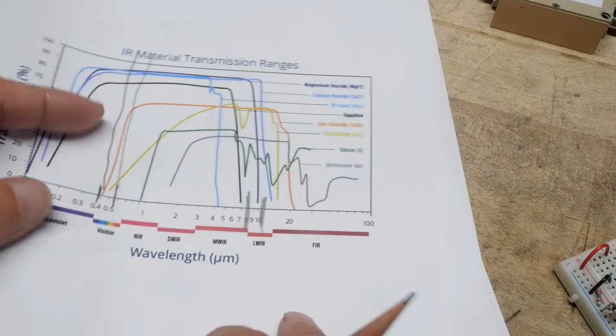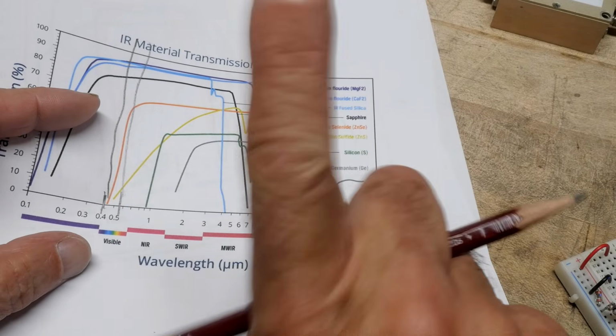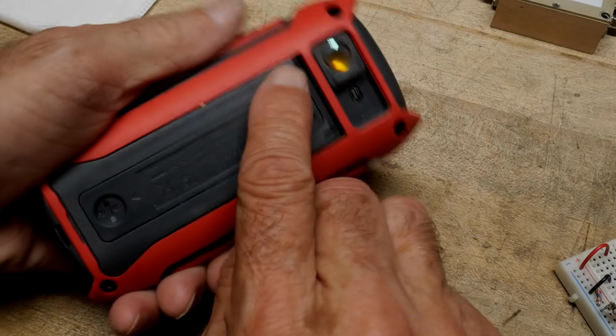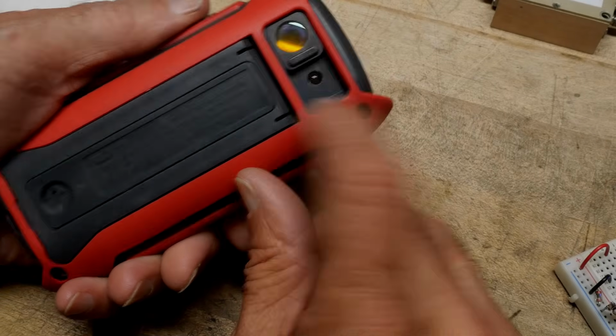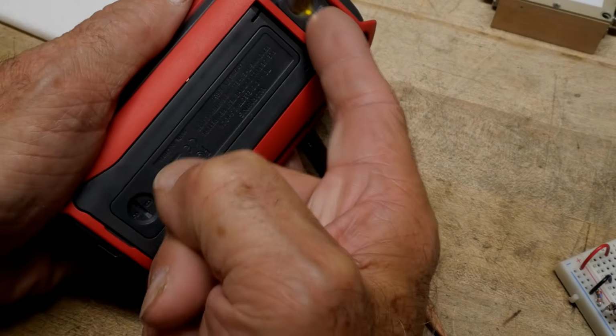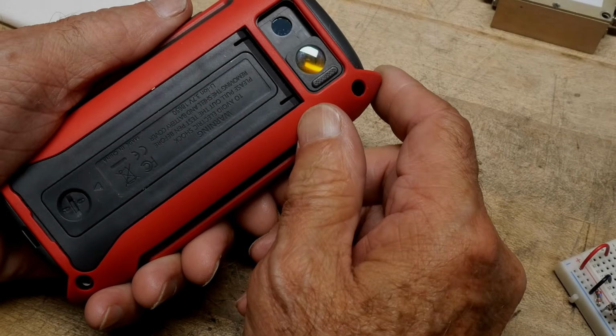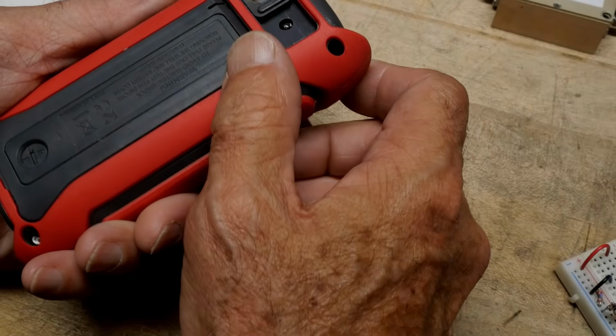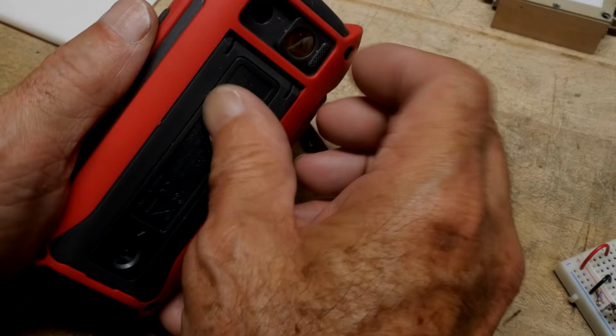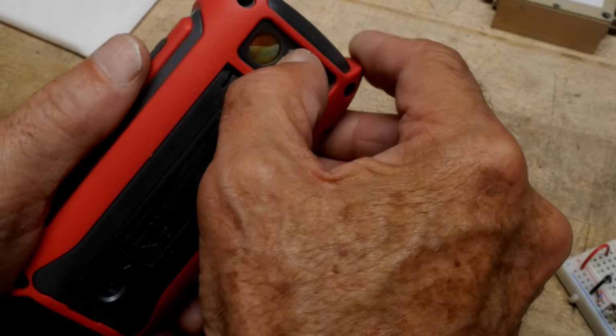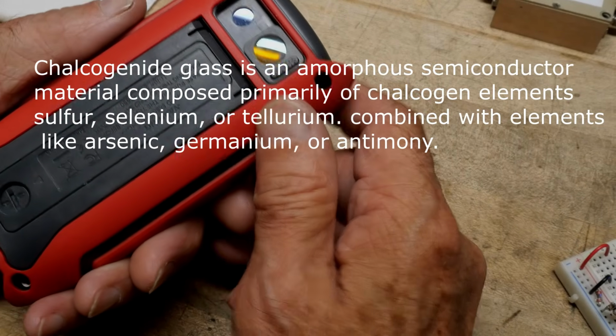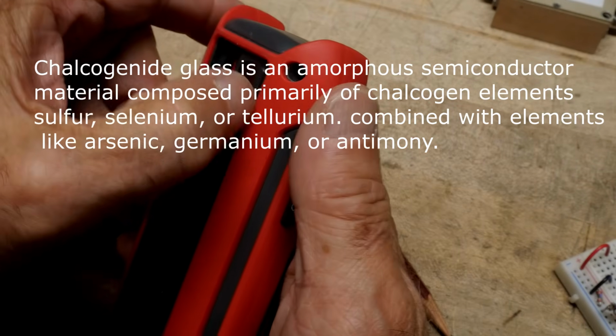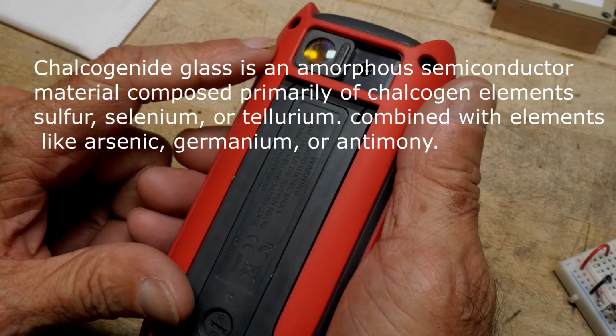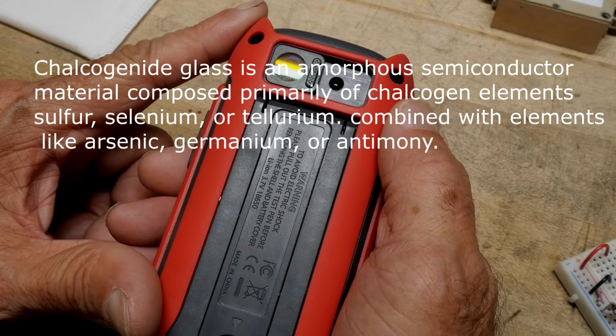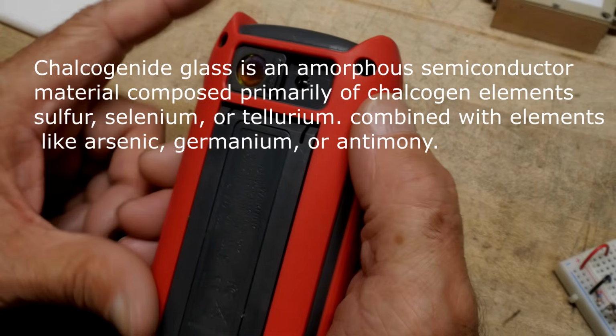All right. And so what do they make lenses out of? Well, they could make them out of zinc selenide, but it's expensive, okay? So they make them out of germanium. This lens here is a germanium lens, and this little lens that pops over is germanium. It's possible that some of these are zinc selenide, but I think it's too expensive. Correct me if I'm wrong, but I think these are germanium. The color kind of makes me want to think it's zinc selenide, though, which it could be. I don't know.